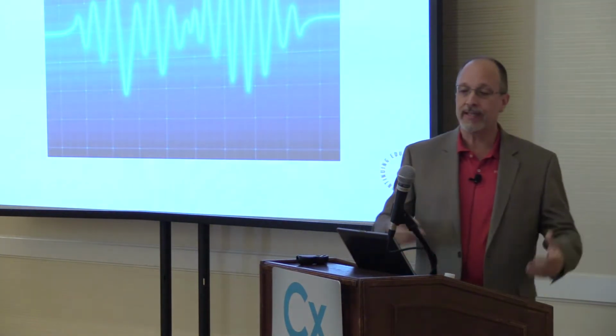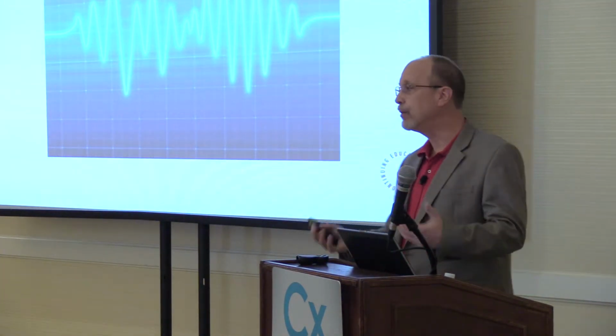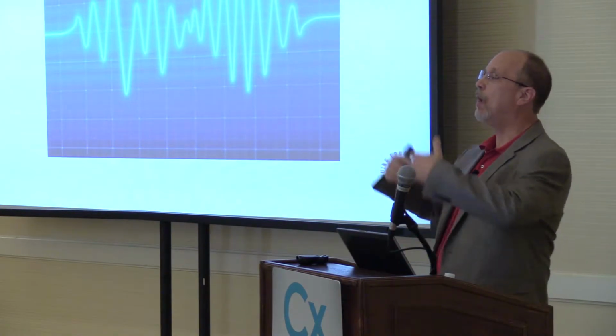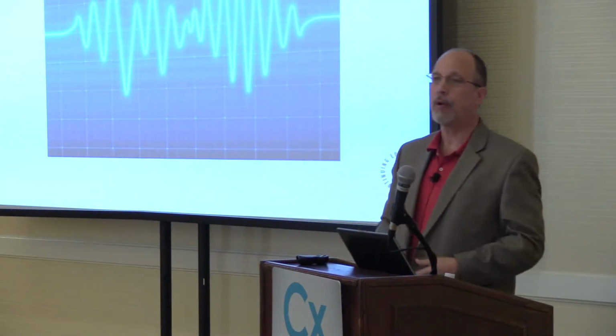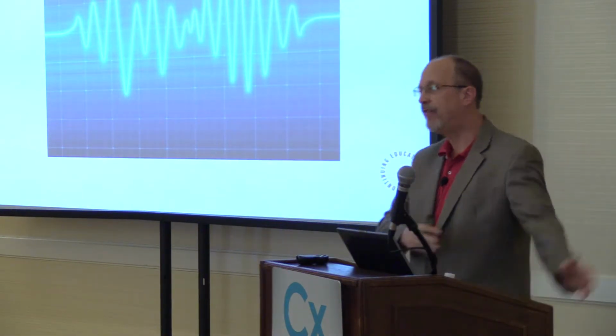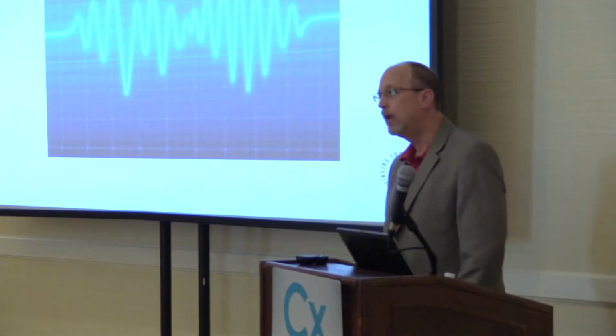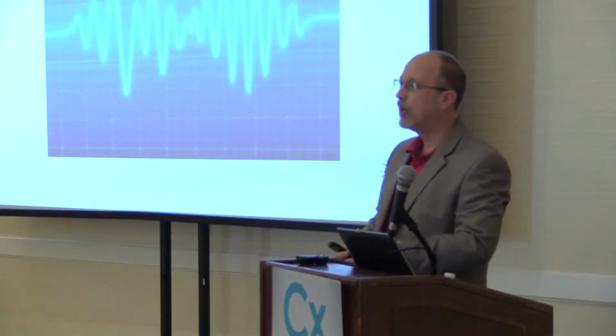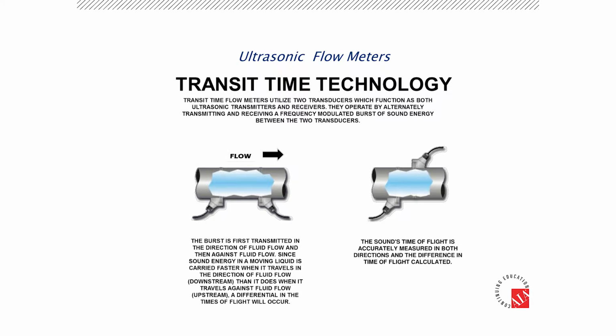And the technology we're using today is primarily a clamp-on type device on the outside of the pipe. It sends ultrasound through the pipe wall into the pipe, and it measures how fast the process liquid is going. And if we know the diameter of the pipe, we can calculate the volumetric flow, or the gallons per minute.